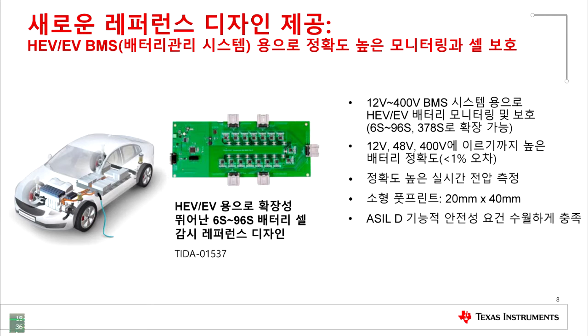Footprint is also of major importance: 20 by 40 millimeters for a single BQ79606A, which is the part used here. You see it 16 times on that board, 16 times 6, so up to 96S support. Each of these small squares is the 20 by 40 millimeters, an important size, as the battery management needs to be built into the battery module, which is space constrained.